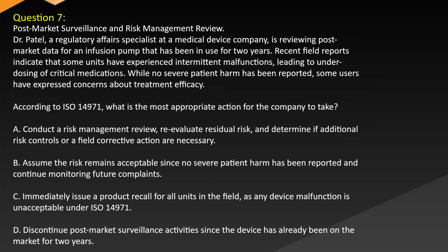Post-market surveillance and risk management review. Dr. Patel, a regulatory affairs specialist at a medical device company, is reviewing post-market data for an infusion pump that has been in use for 2 years. Recent field reports indicate that some units have experienced intermittent malfunctions, leading to underdosing of critical medications. While no severe patient harm has been reported, some users have expressed concerns about treatment efficacy. According to ISO 14971, what is the most appropriate action for the company to take?